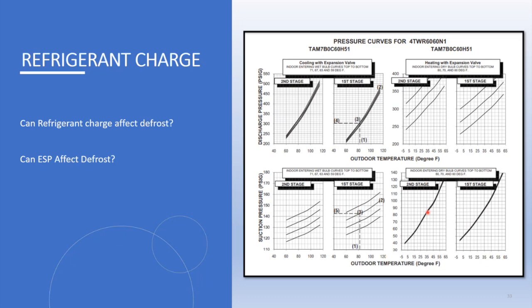Usually the first thing I do during a defrost troubleshoot is put it into a forced defrost and see what happens. First, I'm going to see, okay, when I force a defrost, does it go into a defrost? If it does go into a defrost, does it melt that ice? If it melts all the ice, you probably have something going on with your sensors or defrost board because it's not initiating a defrost. If it goes into a defrost and doesn't melt the ice, maybe it's a charge related issue or metering device or something else going on.